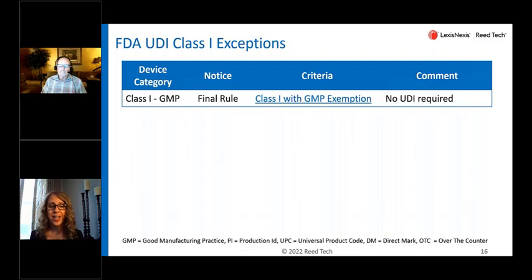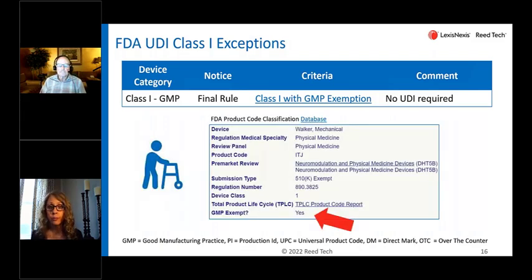Starting with the Class I devices that are GMP or good manufacturing practices exempt. So we're often asked the question, how do I determine whether or not my product meets the GMP exemption or not? So what we did is under the criteria, you'll see that live link. It says Class I with GMP exemption. That is a live link. You click in there and you're brought to the FDA product code classification database. There you're able to enter either a device description, and in the example below, we used mechanical walker, or you can use the 3-letter product code, and that would be ITJ. Either one of those, you would enter that information, about what you're looking up, and it will bring you to this information here. And it provides valuable information about the device product code that it's associated with, including whether or not your device, what the status of the GMP of your device is.